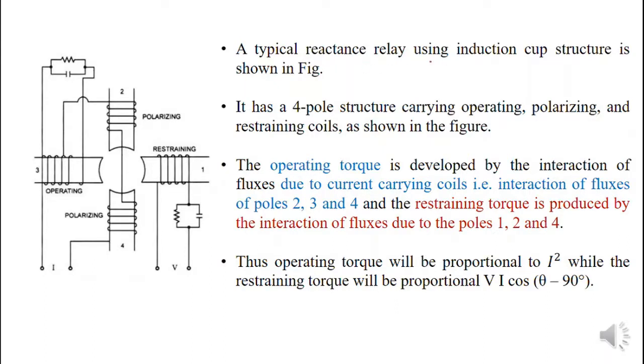A typical reactance relay is shown here using an induction cup structure. It has a four-pole structure — poles 1, 2, 3, and 4 — carrying the operating, polarizing, and restraining coils. The restraining coil is energized by the PT (potential transformer), while the operating and polarizing coils are energized from the CT (current transformer). The operating torque is developed by the interaction of fluxes due to current-carrying coils 2, 3, and 4, which receive the operating and polarizing coils fed from the CT. The restraining torque is produced by the interaction of fluxes due to poles 1, 2, and 4 — a combination of restraining coil plus polarizing coil.